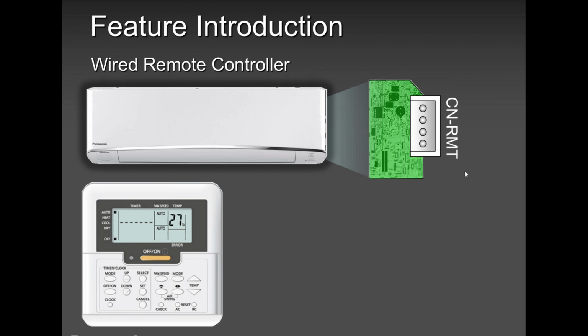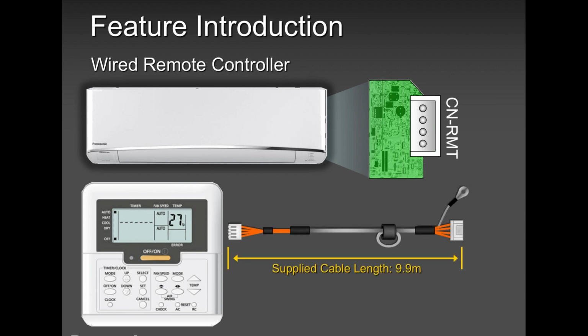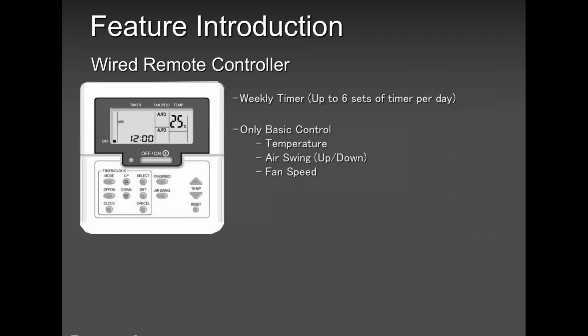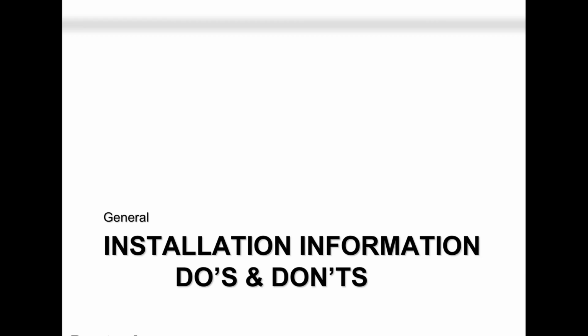So always remember, CNRMT stands for CN remote controller, and this remote controller in the box comes with almost 32 feet of cable. It's nice to use the cable that comes with the thermostat because it's from the factory, nothing like factory. And it has the weekly timer, the basic temperature control, air swing, error codes, and you name it.